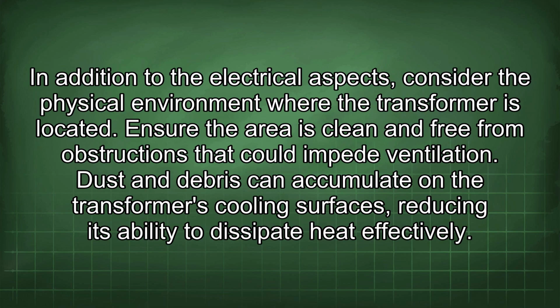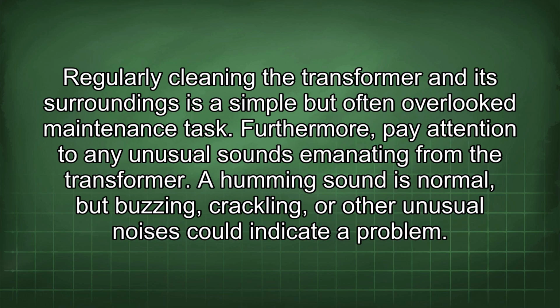In addition to the electrical aspects, consider the physical environment where the transformer is located. Ensure the area is clean and free from obstructions that could impede ventilation. Dust and debris can accumulate on the transformer's cooling surfaces, reducing its ability to dissipate heat effectively. Regularly cleaning the transformer and its surroundings is a simple but often overlooked maintenance task.